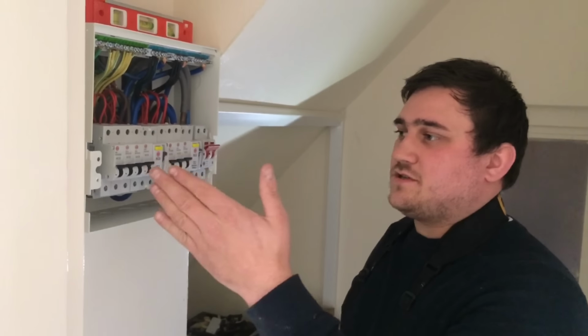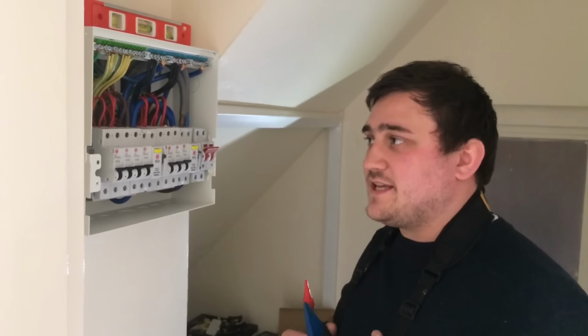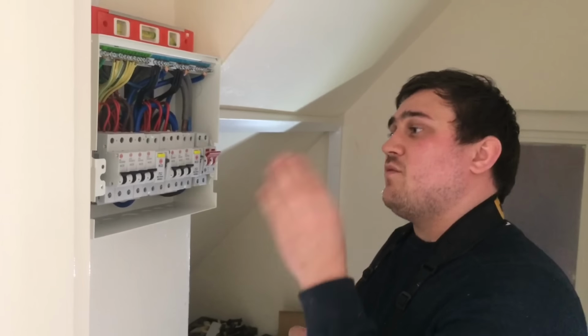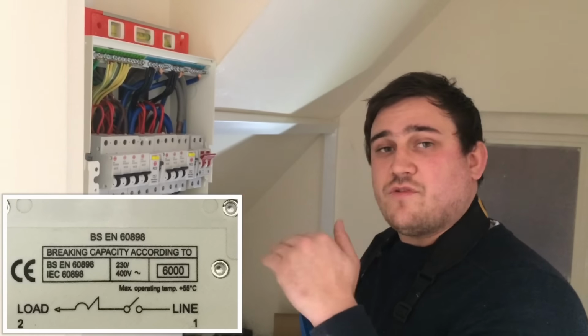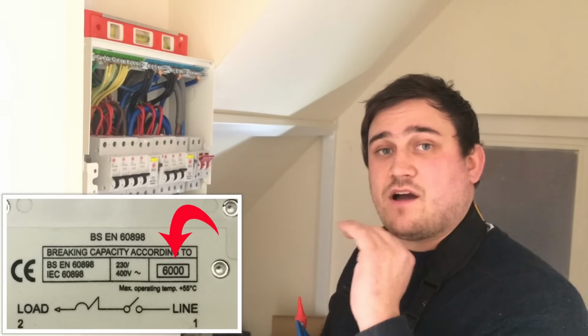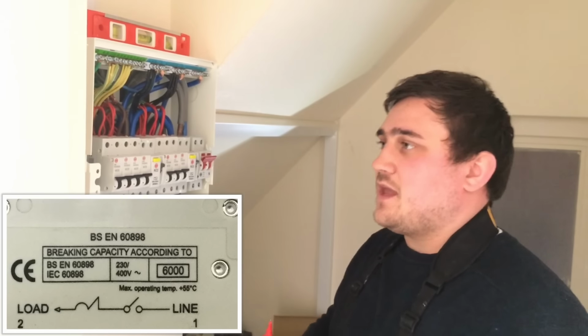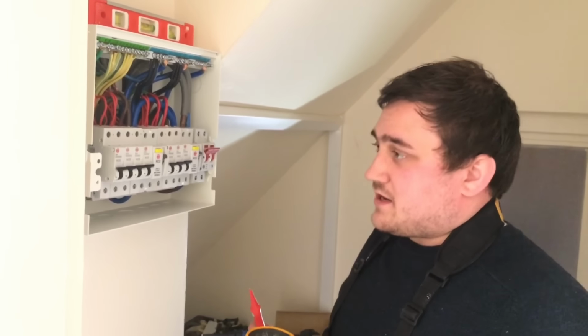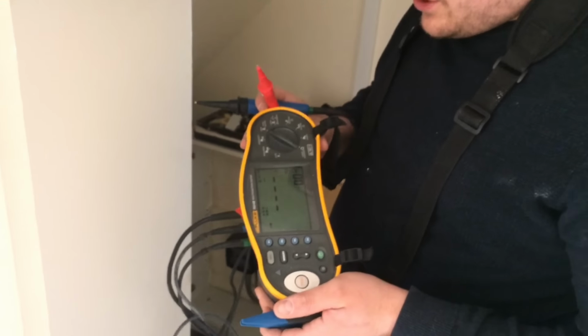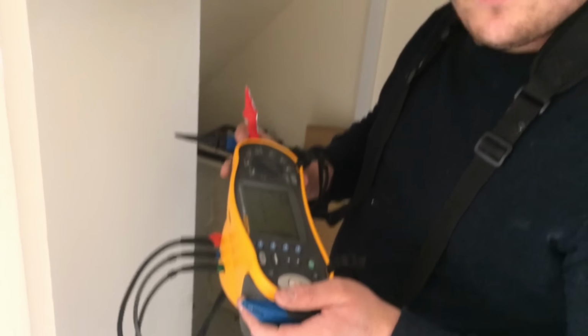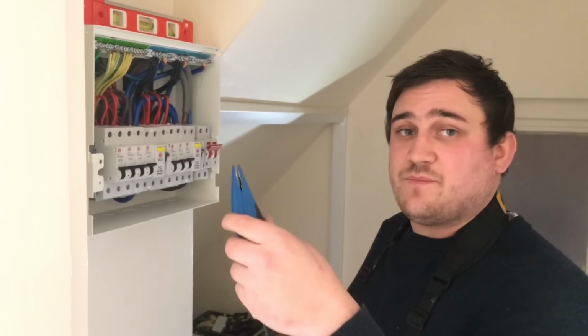Now we've energised all of our circuits, we're now going to do a PFC for the top of our breakers. When we was installing them, we looked at the side of the breaker in this case, and they are a breaking capacity of 6 kA. For this, because of RCDs in the circuit, I'm having to do a 3-lead no-trip test on my tester for when we do our PFC and PSC.